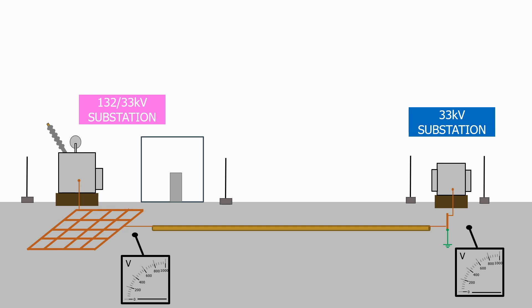The first problem is that anything connected to the grounding grid of our substation that has gone faulty will also rise by the same GPR amount. Here we have our 132 to 33kV substation connected via an underground cable to a 33kV distribution substation. If a fault now occurs on the main station, the voltage potential of our grounding grid will now increase to 960 volts.